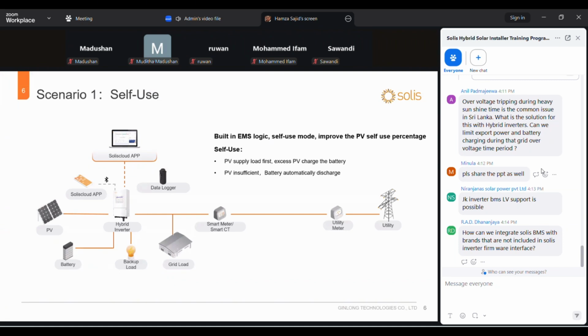Okay, in the portion where we set the backflow enable, there is also an option available for the export power control. So you can mention how much watts you want to send back to the grid. So you can control these things. And for the over voltage, with the hybrid inverters, we have a wide range of voltages for the high voltage upper limit and the lower limit. So it can easily sustain the high voltage or the lower voltage. So you can also set them according to the grid code available in your country.